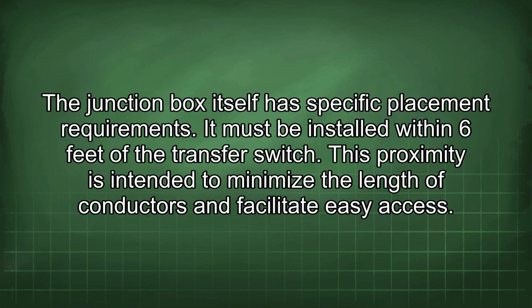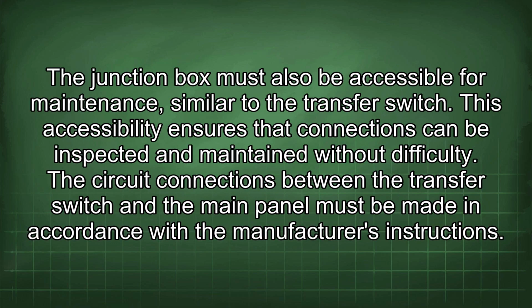The junction box itself has specific placement requirements. It must be installed within 6 feet of the transfer switch. This proximity is intended to minimize the length of conductors and facilitate easy access. The junction box must also be accessible for maintenance, similar to the transfer switch. This accessibility ensures that connections can be inspected and maintained without difficulty.